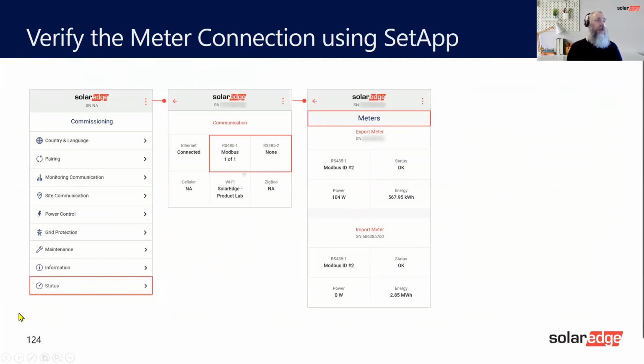When you've done all that, you can look in the status. You can see Modbus 1 of 1 because we're in RS485. You can see it's RS485, Modbus ID 2. That's perfect. Then we can see the import meter, the serial number. We can see a status is okay and what it's doing.